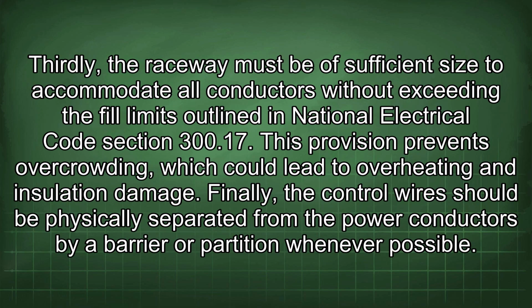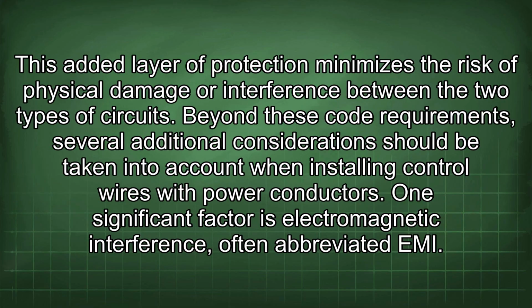Thirdly, the raceway must be of sufficient size to accommodate all conductors without exceeding the fill limits outlined in National Electrical Code Section 300.17. This provision prevents overcrowding, which could lead to overheating and insulation damage. Finally, the control wires should be physically separated from the power conductors by a barrier or partition whenever possible. This added layer of protection minimizes the risk of physical damage or interference between the two types of circuits.